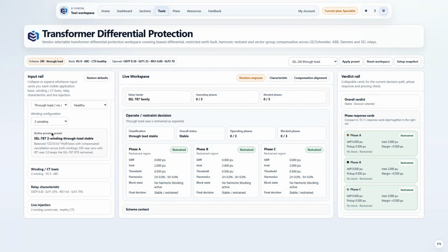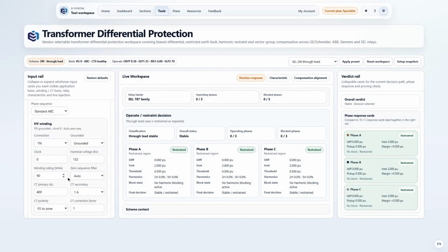The scheme itself: a 90 MVA transformer, 132 over 33 kV. The HV winding is star, clock 0. The LV is delta, clock 9. HV CTs are 400 to 1, LV CTs 2000 to 1. The relay has to line all of that up before it can compare a single amp.